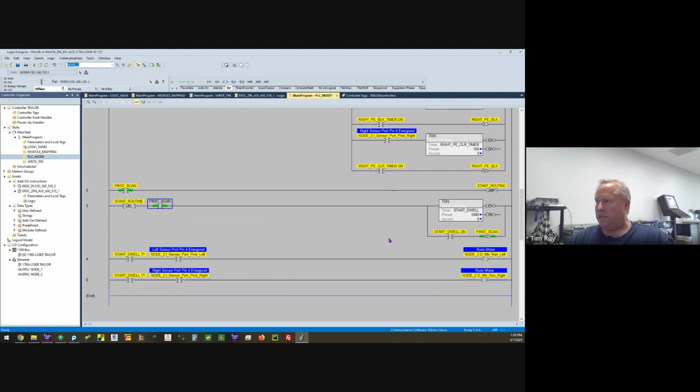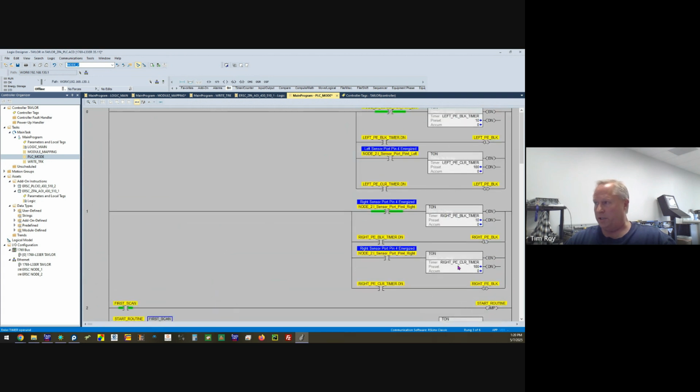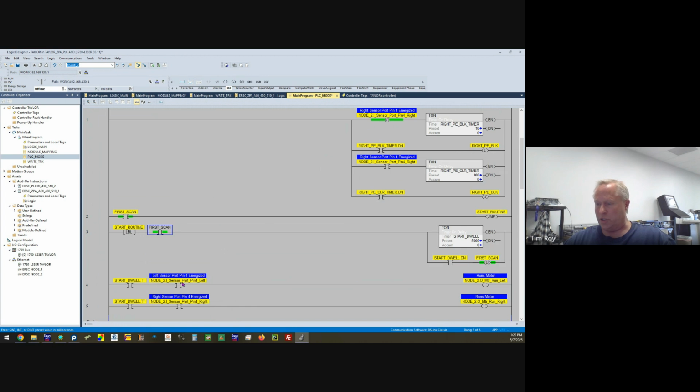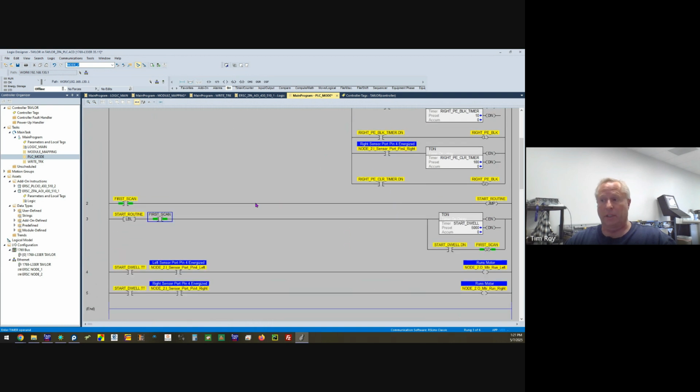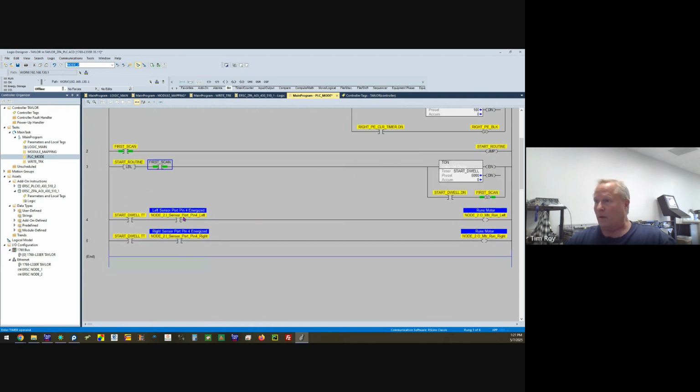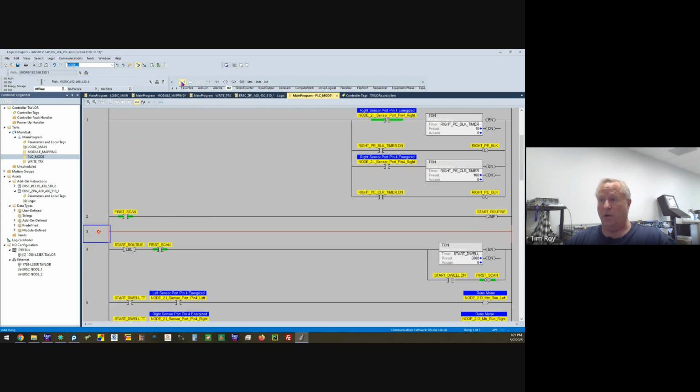And so this is the basic. Grab our sensor status. And notice how during this start dwell where I'm searching, I'm not using the photo-eye logic. I'm using the direct sensor bit. I like doing that so it stops quick, sees the eye and stops. I'm not relying upon timers at this point. So now it's time for our actual logic. The logic will go in between the jump and the label.